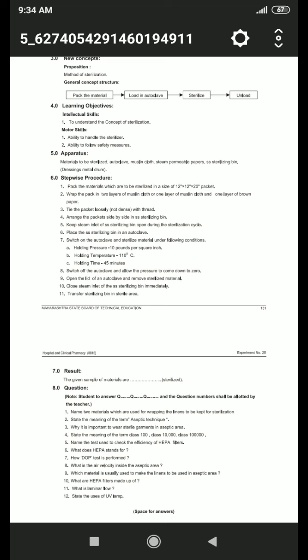Then, the name of the test used to check the efficiency of HEPA. HEPA means high efficiency particulate air. The dispersed oil particulate, that is DOP, scan testing, also known as leak testing, is one of the most quoted methods by industry standards. The test is recommended to be repeated at regular time intervals to verify the continued efficiency of the filter. Okay, these are the efficiency tests of HEPA.